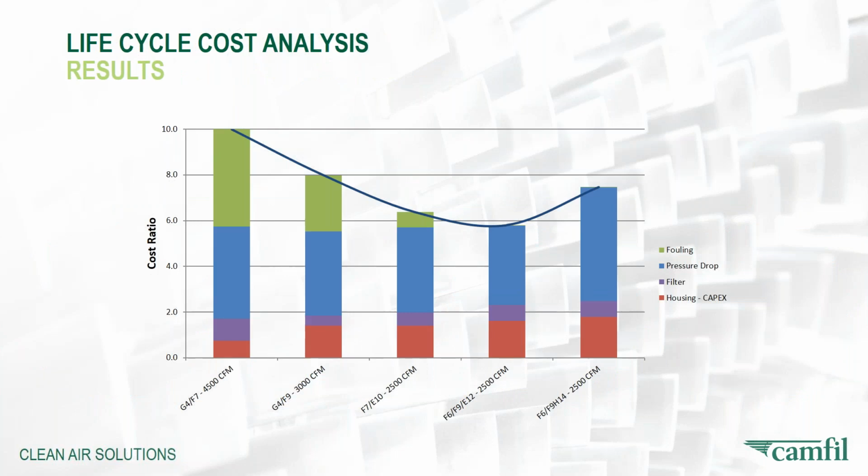So we do all of these things I mentioned in the previous slides just so we can come up and show you a nice chart. This is a chart that was derived several years ago from an exercise we did with LCC to create a cost ratio model for a customer. And what you see are 5 different filter solutions. On the far left-hand side is the package the site was currently using, which was a high velocity, mid-grade efficiency filter package.